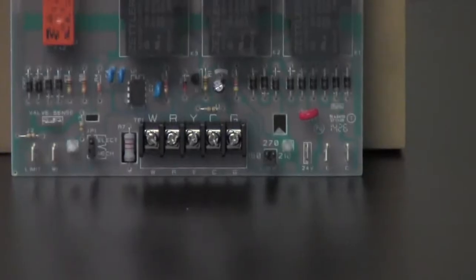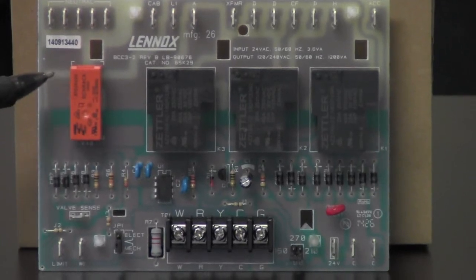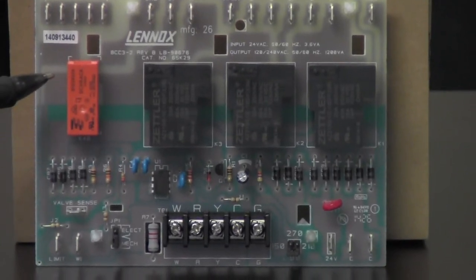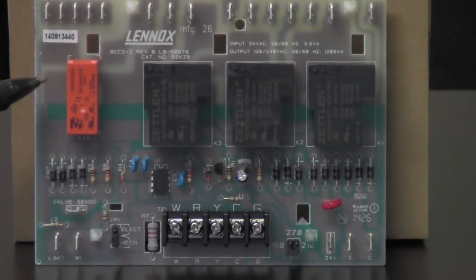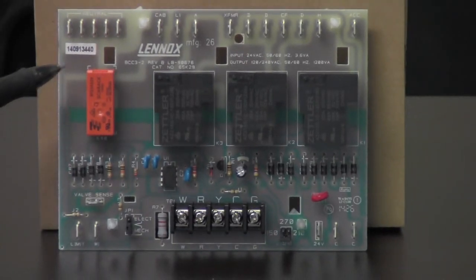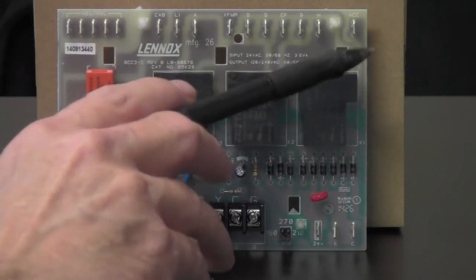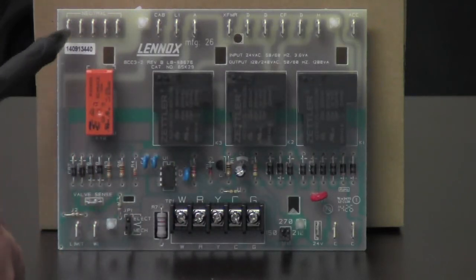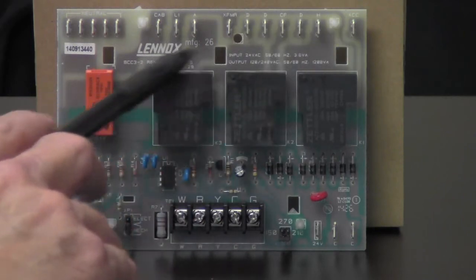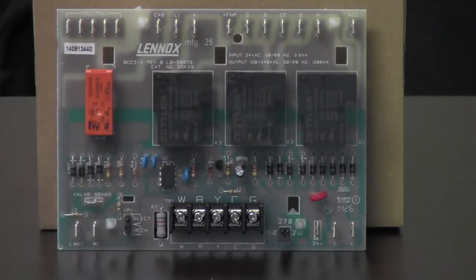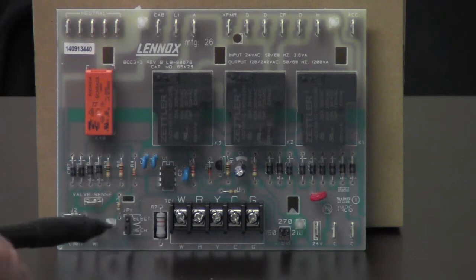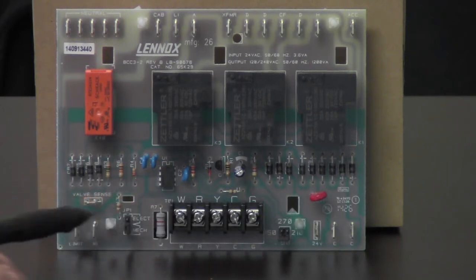Okay, so this control right here is divided. This is a blower control board. This one happens to be the BCC3. Now this control is divided up into two sections. Up on the top section this is all our 120 volt line voltage. The bottom side of this board down here is all of our 24 volt or our control voltage.